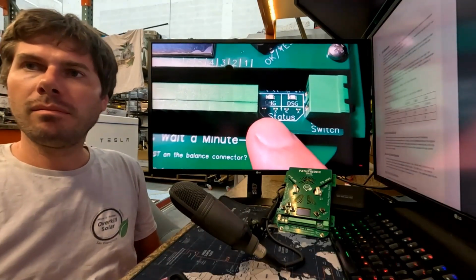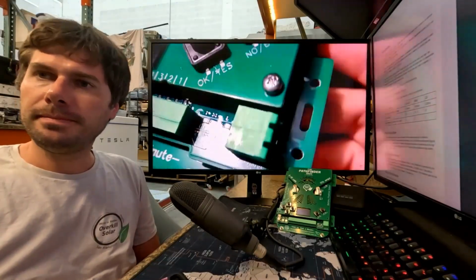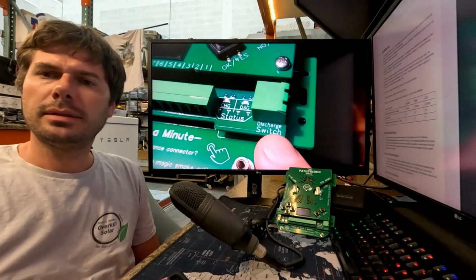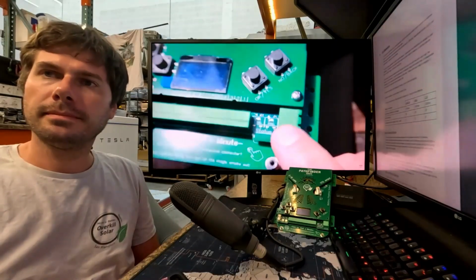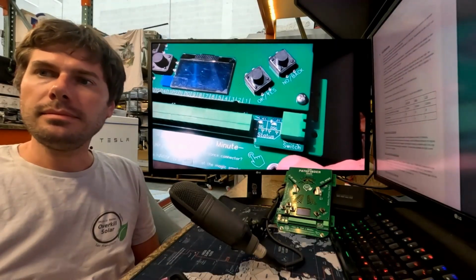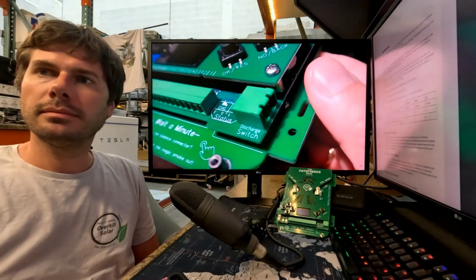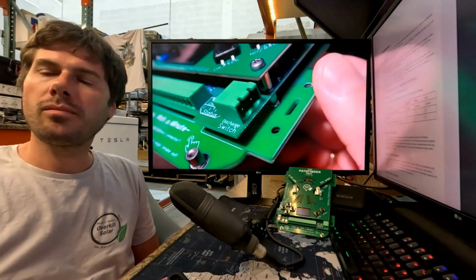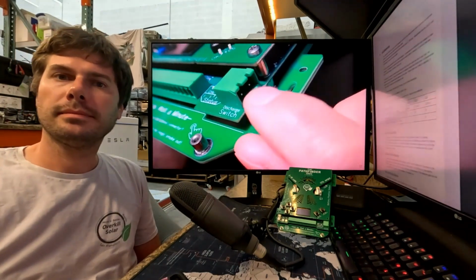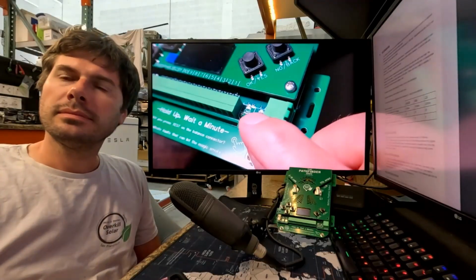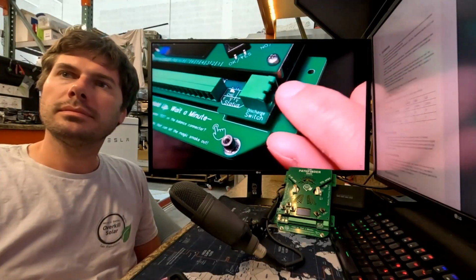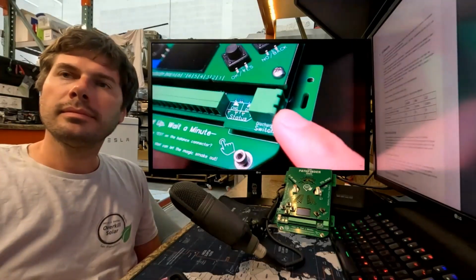On this side we've got two LEDs for charging and discharging, and a discharge switch. If you connect these two pins, discharge will actually turn off. This is very useful and handy if you frequently connect inverters to the BMS. You just close the switch between these two contacts, discharge turns off, you connect your inverter, and then turn the BMS back on. More about this feature later.